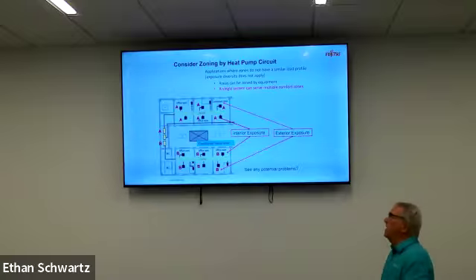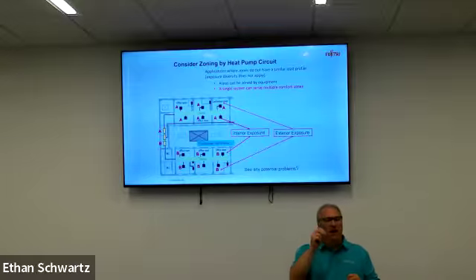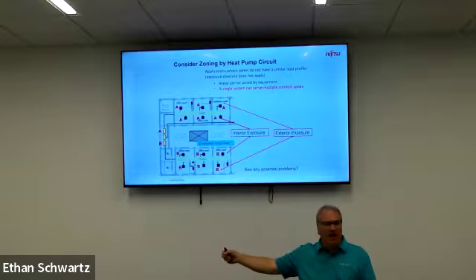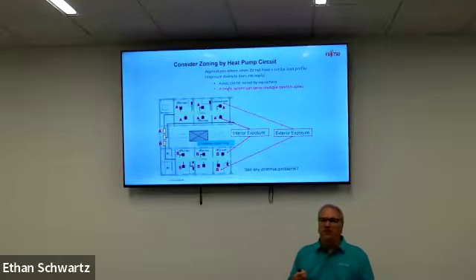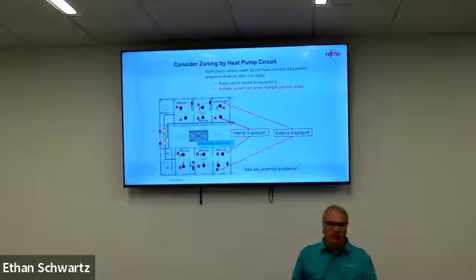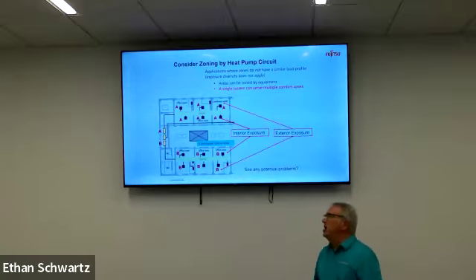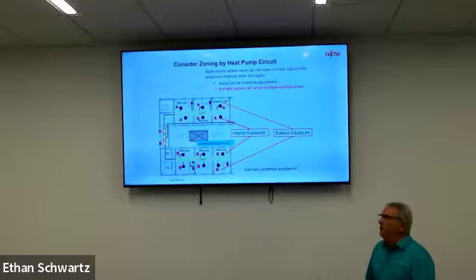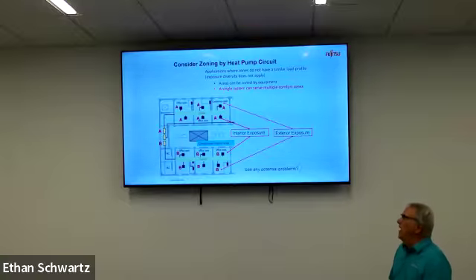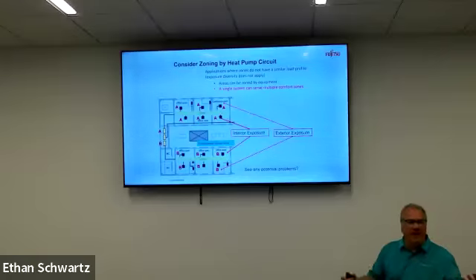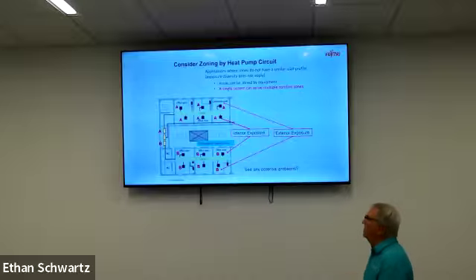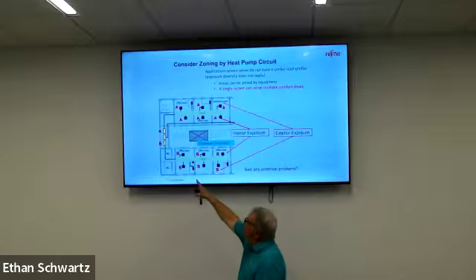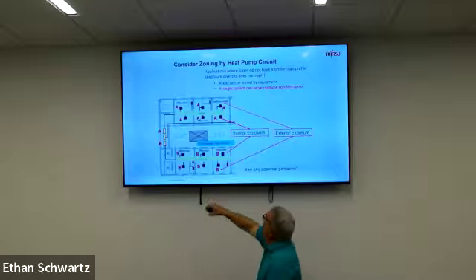And then the other thing that I want you to think about, because I said that heat recovery brings you into the 3-phase realm that may not be available. So I want you to think about zoning by heat pump circuit. So a total tonnage comes up for a given structure. It doesn't matter if it's a large home or small for that matter, or an office building, but there's some heat loss, heat gain, and that's going to be some number of tons.